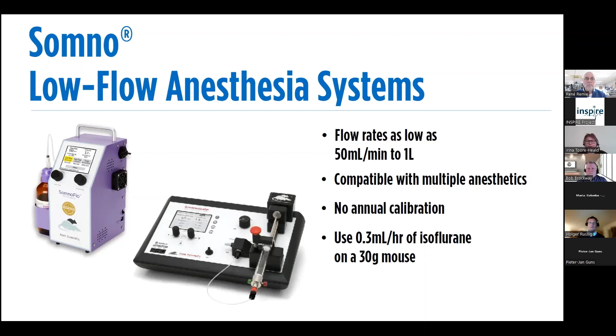So what makes the SomnoSuite a unique system is, as I mentioned, precise delivery of anesthesia and solid state electronic design. As I also mentioned, no annual recertification is required, and it uses room air versus compressed gas. Low flow rates allow you to deliver to the animal exactly what it needs and not over deliver, which also means less waste anesthesia gas exposure, and no one should be smelling isoflurane basically. The system is compatible with both isoflurane and sevoflurane, and the flow rates can go as low as 50 mils per minute and as high as 1 liter per minute.